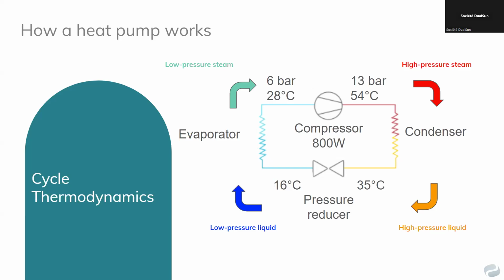In other words, the heat from an external source will be recovered and fed into the thermodynamic cycle to continuously power the heat pump. We therefore have three separated closed circuits. The first upstream glycol circuit, which is the cold source that will exchange heat on the evaporator side of the heat pump. Then the second closed circuit, which is the refrigerant's thermodynamic cycle. And finally, a third and last distinct cycle that exchanges on the condenser side, the production circuits that will meet demands.